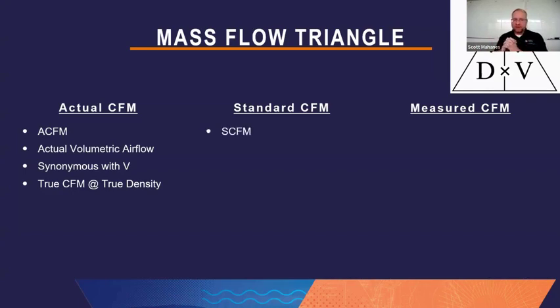Moving on to standard CFM, this is kind of uncommon to us. It's the SCFM value. And really what it stands for, it's the mass airflow CFM equivalent. What's interesting about mass is it's in pounds per minute. We said that earlier. And pounds per minute, we don't have meters that measure that. We don't have scheduled values. Imagine if you had 7.5 pounds per minute shown on a drawing that was next to a grill. Set the grill to 7.5 pounds per minute. None of us would know how to do that. That's not a common thing.